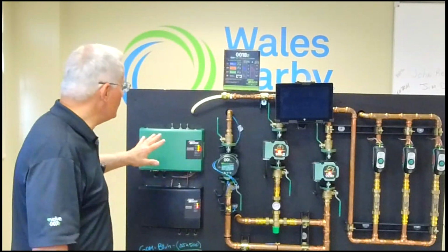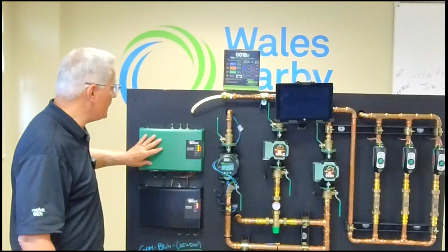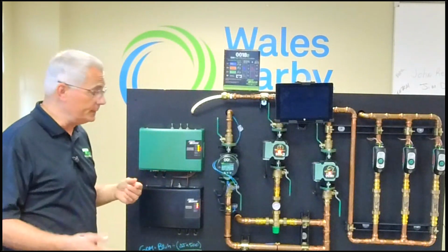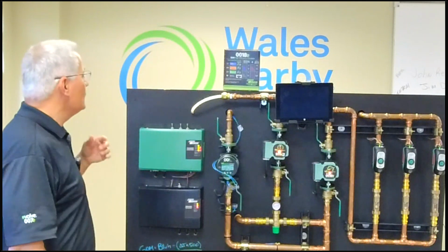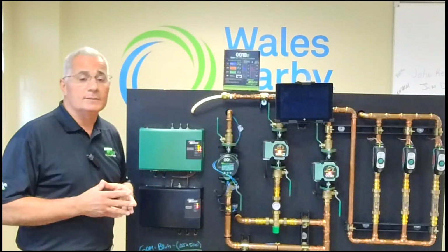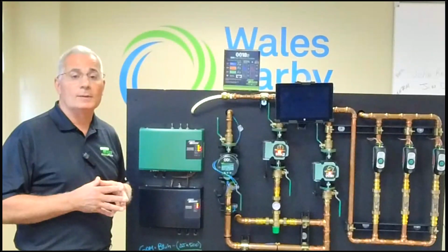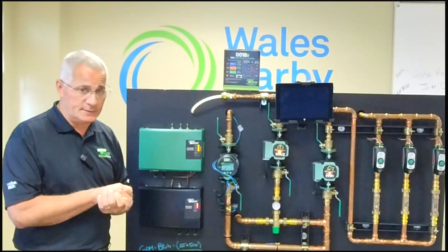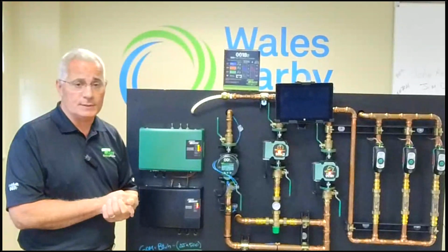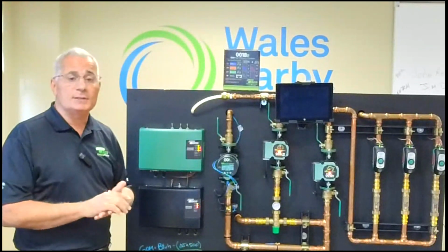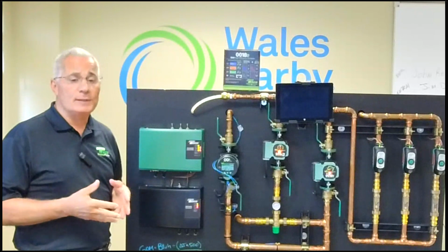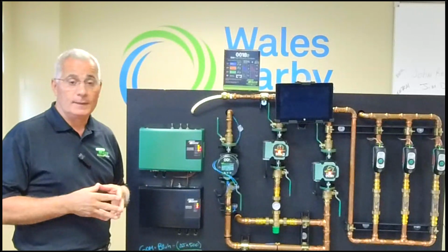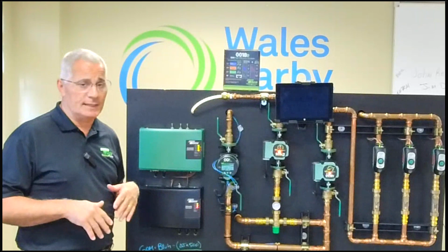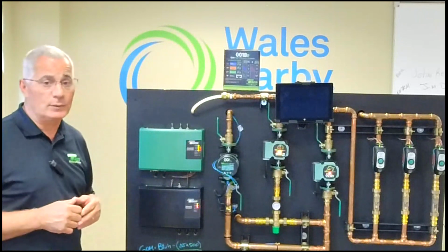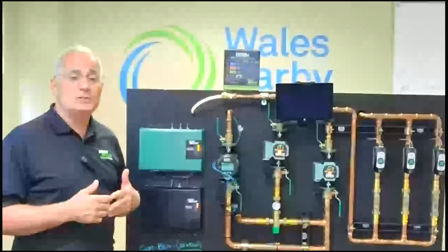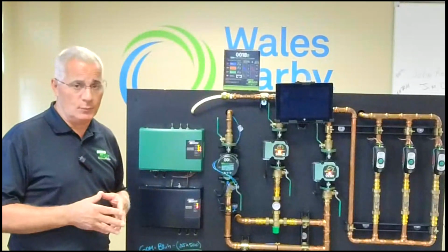All right. The other important feature on these ZVC panels, since we are talking about energy, on the EXPs, we have the ability to plug in some export controls, or in my case, on my boiler at home, which is cast iron, a PC700. So that PC700 is allowing me to put outdoor reset on a cast iron boiler. I'm not changing water temperature because I cannot have that cast iron boiler condense. But what I am changing is the amount of runtime for the boiler.